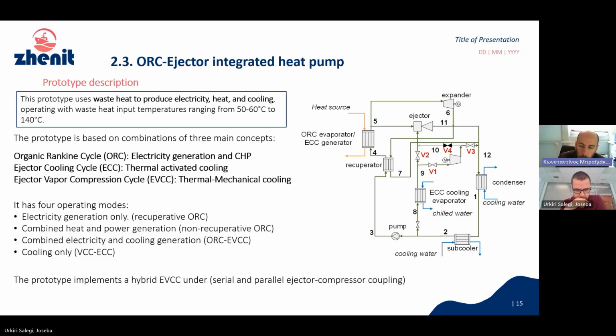Then we have a second technology that's part of this prototype. This technology is the ejector cooling cycle, or ECC in this presentation. And the ejector cooling cycle is a thermally activated cycle. It's very similar to the standard vapor compression cycle. The only difference is that instead of a mechanical compressor, we have an ejector device, and the purpose of this ejector device is to utilize high pressure, high temperature flow that is generated with waste heat to entrain low pressure vapor that leaves the cooling evaporator of the system.